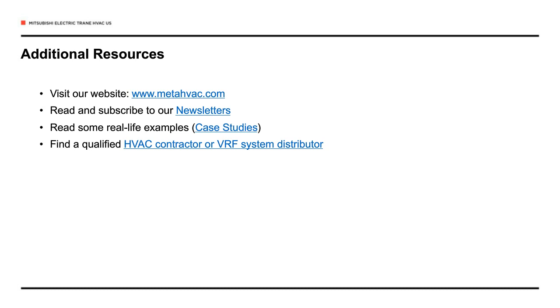However, caution needs to be exercised, especially with air source VRF systems, in dealing with process loads. So if you have process cooling loads that are totally independent of outside ambient, in other words, your load could be 100% if it's 5 degrees below zero outside, there are design considerations that you have to look at. We have a white paper or application note put together that addresses that topic. So the short answer is yes. The long answer is, it depends, and you need to look at the specifics.